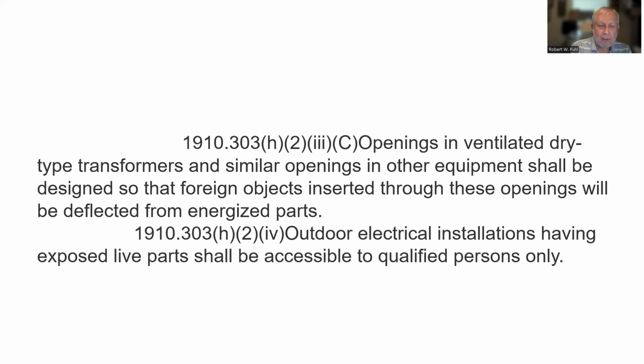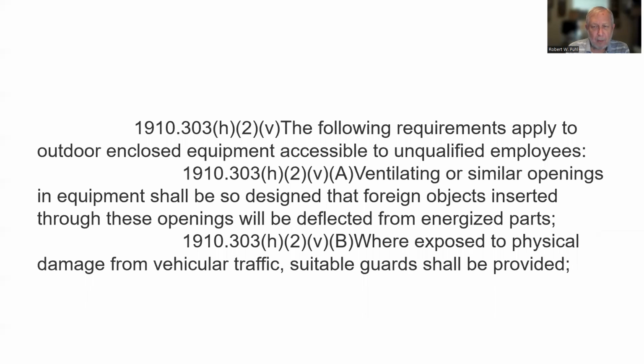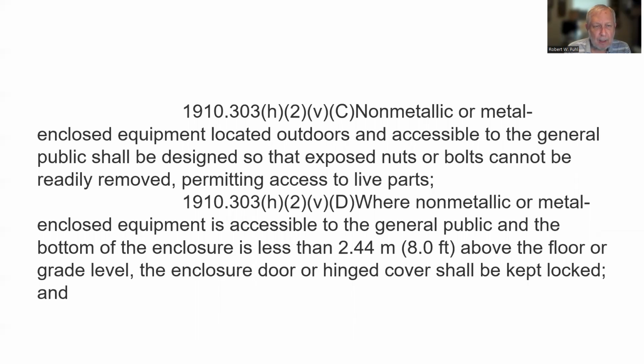Outdoor electrical installations having exposed live parts should be accessible to qualified persons only. The following requirements apply to outdoor enclosed equipment accessible to unqualified employees. Ventilating or similar openings in equipment shall be so designed that foreign objects inserted through these openings will be deflected from energized parts. Where exposed to physical damage from vehicular traffic, suitable guards shall be provided. Non-metallic or metal enclosed equipment located outdoors and accessible to the general public shall be designed so that exposed nuts or bolts cannot be readily removed, preventing access to live parts. Makes sense too, doesn't it?